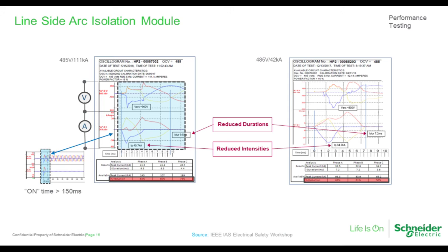This is one of the most important benefits of self-clearing. We do not care what the trip settings are of the upstream device. It could be 3 cycles, 30 cycles, 3 seconds, or even longer, and the ArcBlok clearing time of less than 1 cycle always applies. The next upstream device does not even have to open. The module is designed to reliably self-clear for any valid voltage or available fault current of the breaker that it's attached to.